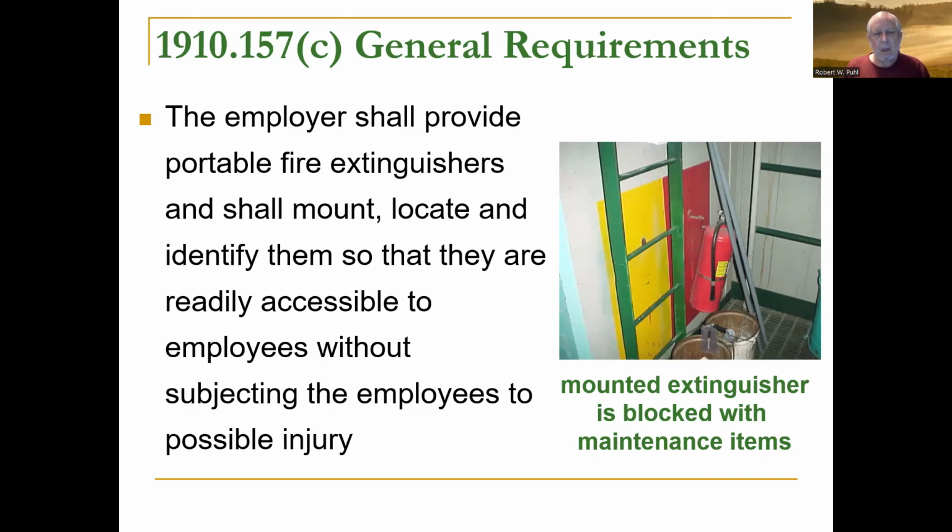It doesn't tell you here how high to hang them. There are height requirements, and I think they vary by state or maybe locality, for the top of the fire extinguisher, at least if we're in California. And generally speaking, you want to put them where you're not having to go into a fire to get the fire extinguisher. They're going to be basically on your way out, like near the door somewhere, so that even if you can't get the fire out, you can still get out.